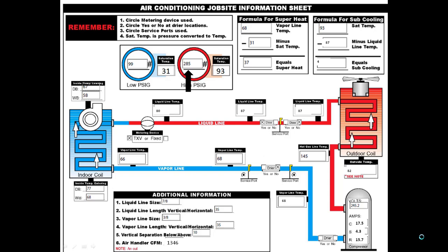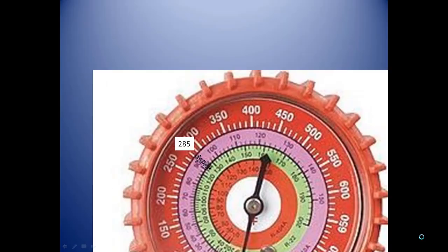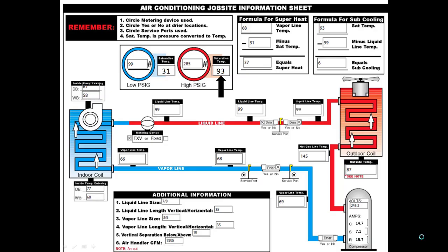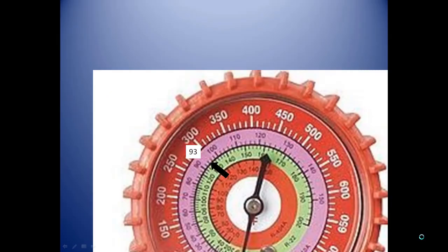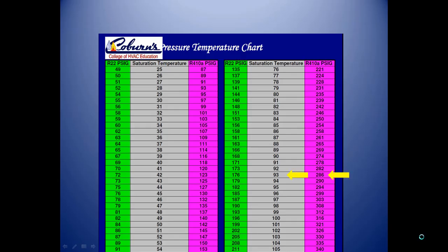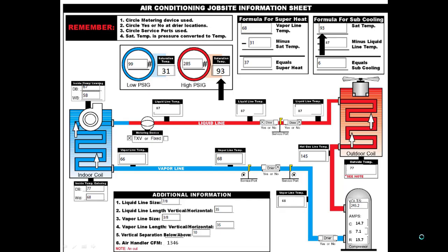Next, we move on to the high side. On the high side, we need the gauge manifold pressure, and also the saturation temperature, which can be gotten off the gauge also, or you can go over to the pressure temperature chart and convert it there. We'll place those numbers in both places here on the job site information sheet.